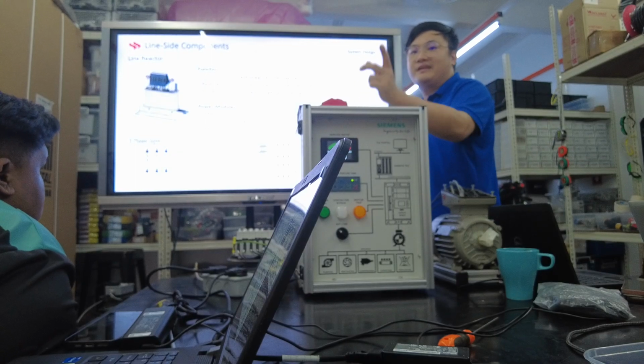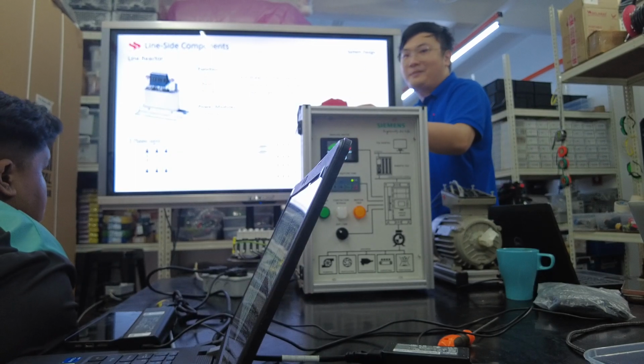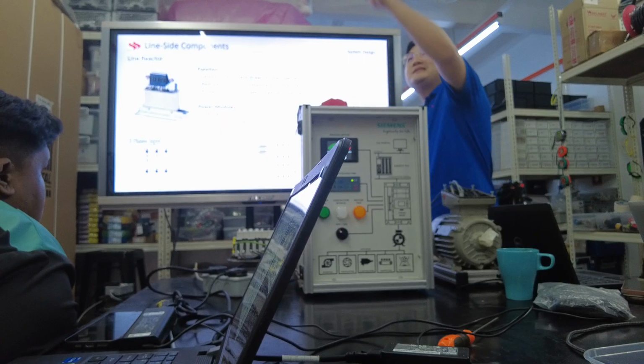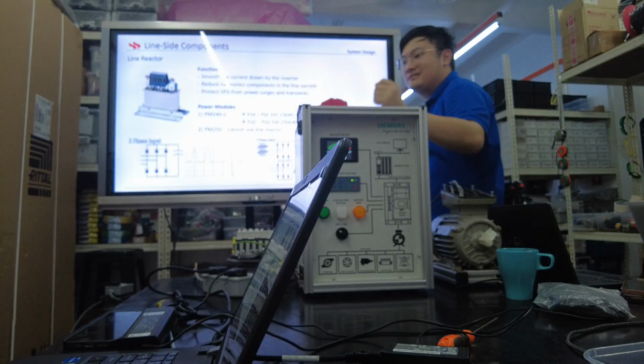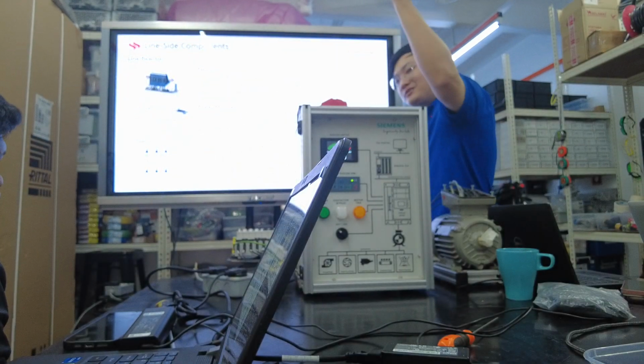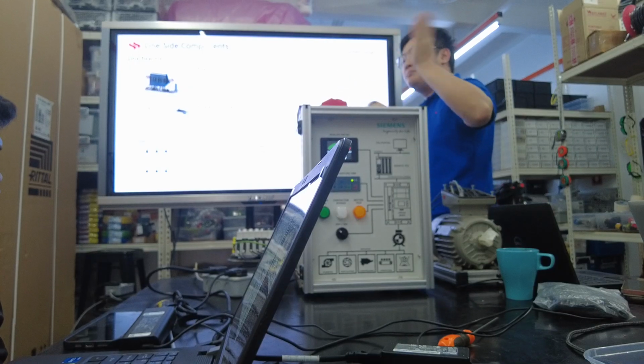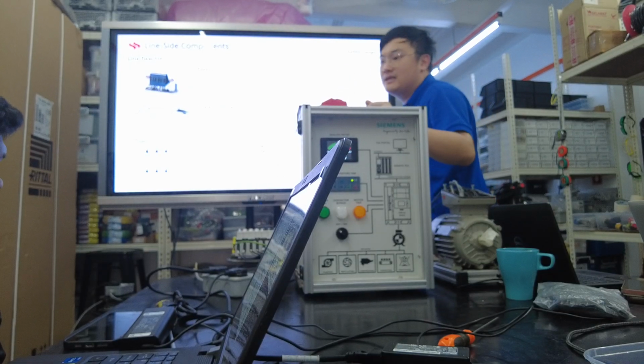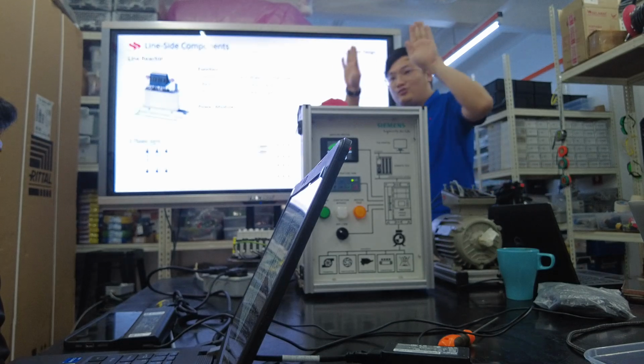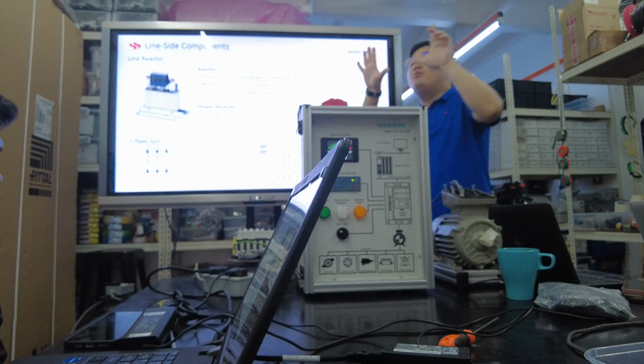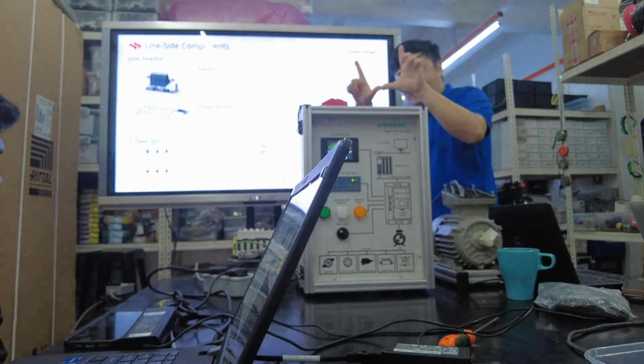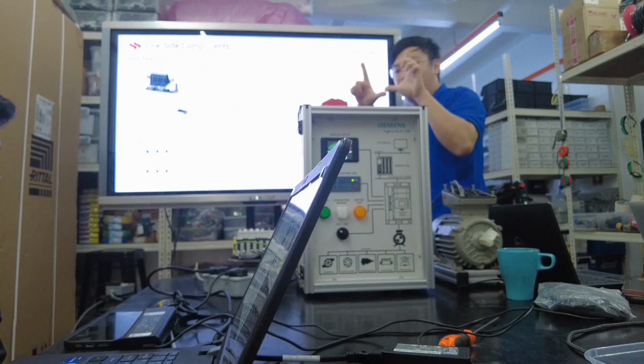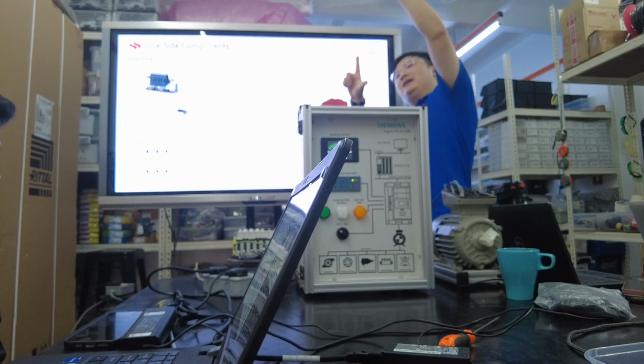Usually caused by power switching. Selalu jadi apa? TNB switching. Kalian perasan kan kalau di rumah tiba-tiba macam lampu tu terang sikit ataupun kipas tiba-tiba pusing laju, okay, back to normal. This is causing what? Because they're doing the make-before-break switching on the TNB side. Make-before-break switching is what? You got two transformers, you got momentary close within two transformers. So your transient will be big. Dia punya transient current dulu akan naik.